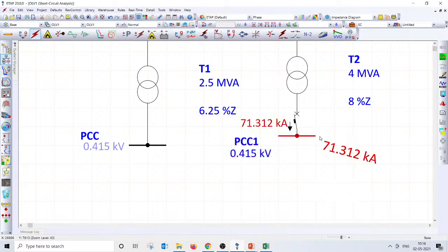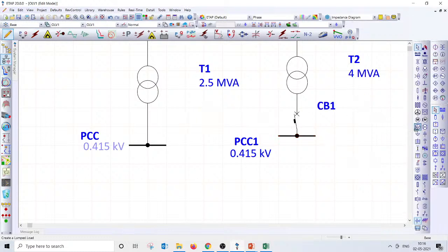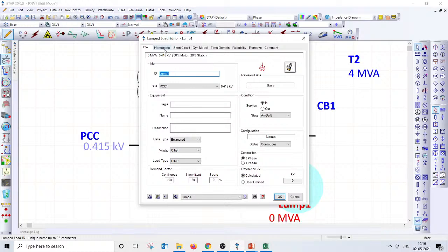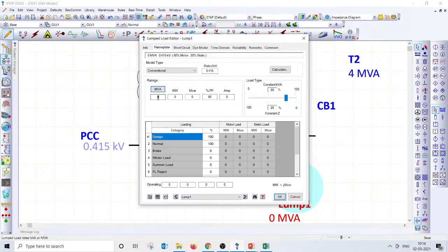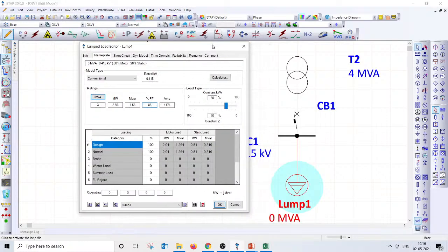If your fault current contribution is 71 kiloamps, and though it is not the right way to do it, let me put, for example, the loading on the transformer at 3 MVA. You need to model it in detail, but because of time constraints I am just putting 3 MVA here at 0.85 power factor, assuming that 80% of the load is constant power load, which is motor load, and 20% is constant impedance load. This changes drastically with the kind of industry you are dealing with, right?